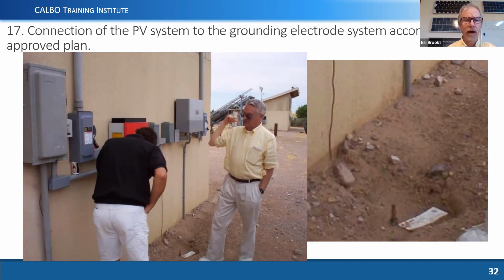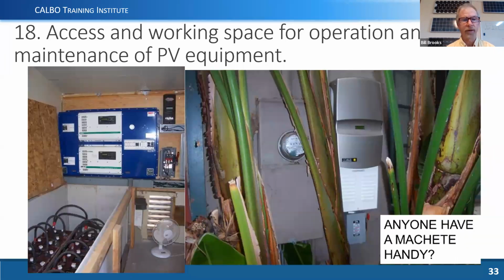and even if it has an existing ground rod, many communities will require an additional ground rod installed 6 feet or more away from the original ground rod. So you have at least 2 ground rods. And that has nothing to do with solar, quite frankly. It's really just a general electrical requirement. And it is true that there are a lot of substandard grounding at homes in California. And so if you're the first person to do an electrical project at a home, in an older home in California, then installing grounding electrodes is not an uncommon thing to have to do.